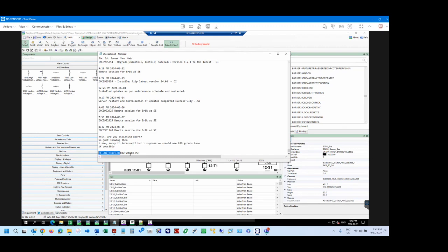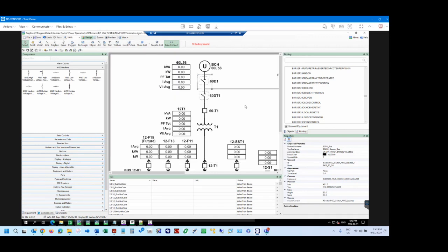It's taking the full tag name, which is exactly what you need for this process to work. The active condition needs to be the full tag name. And so that's in there. You can also put qualified flags on that. Let's say that tag name was an analog instead of a digital, like voltage, and I wanted to say it's active when voltage is above 0 and inactive otherwise.